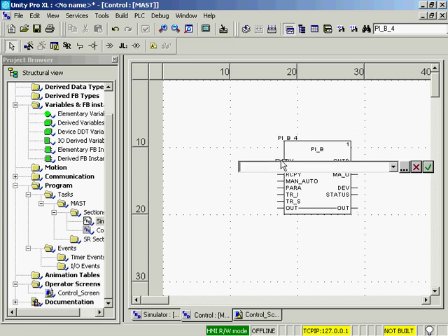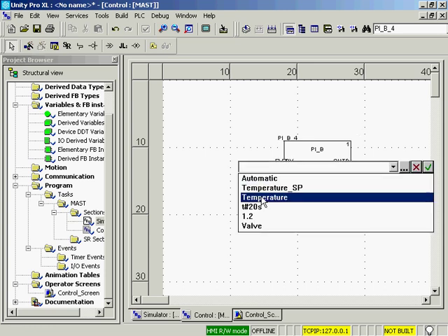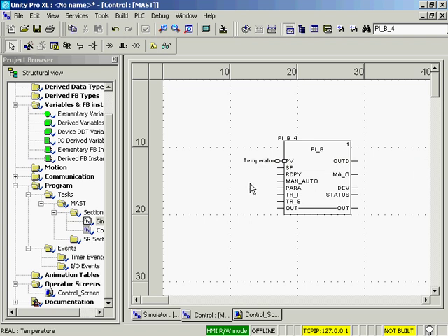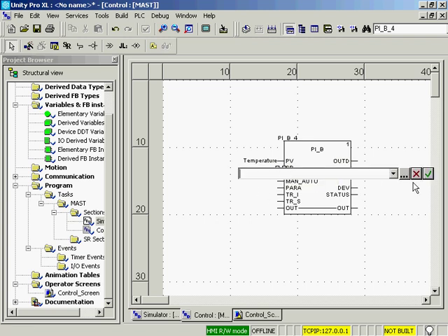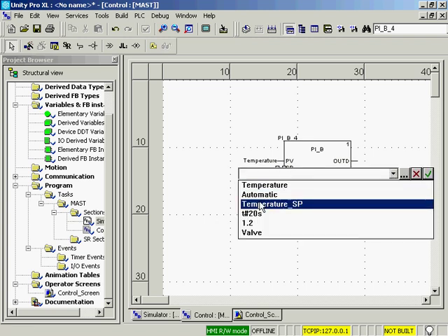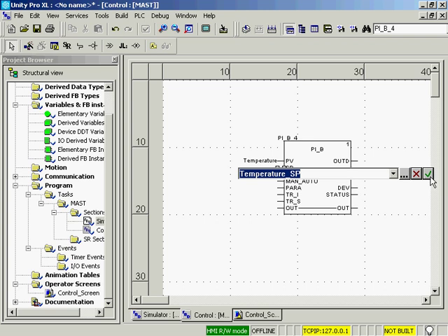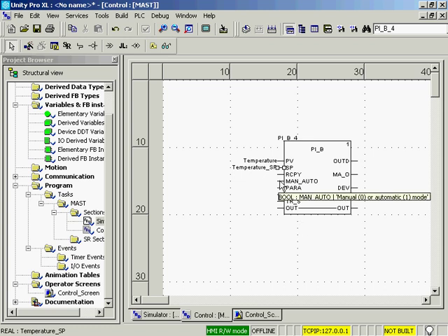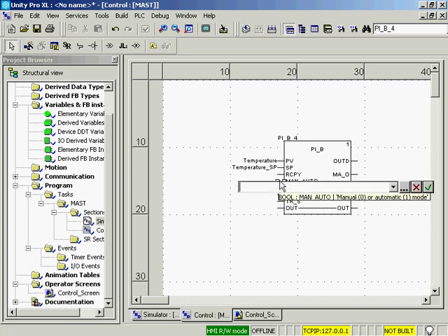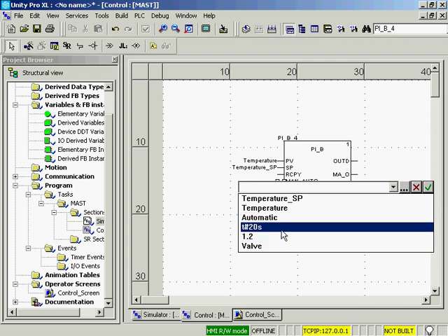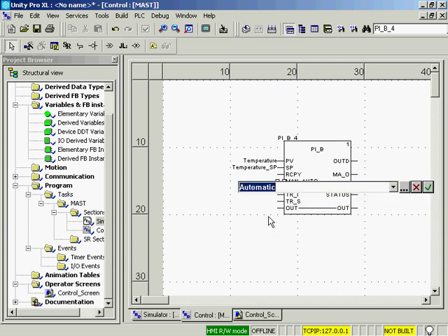The process variable in this example is going to be a temperature. This temperature is a real value. The setpoint we'll just call temperature setpoint. Next we'll create an automatic mode variable. When the function block is in automatic mode the control algorithm is running. In manual mode the output is controlled manually.